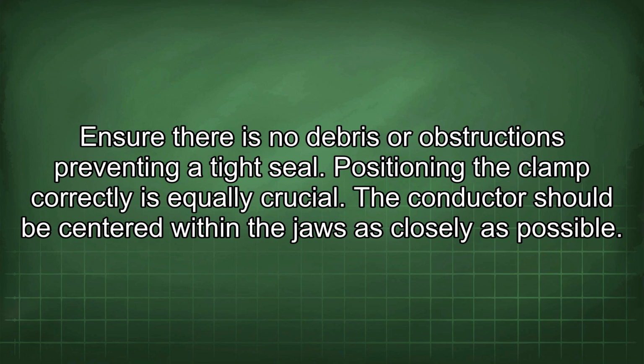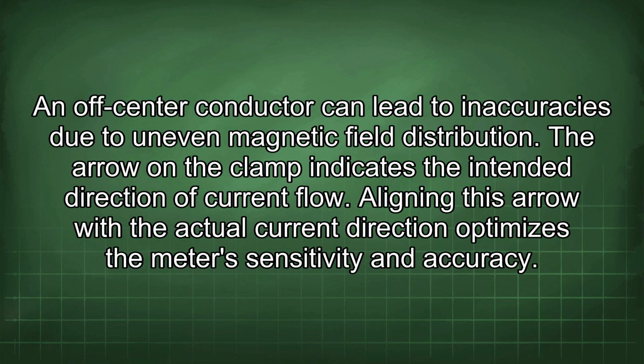Positioning the clamp correctly is equally crucial. The conductor should be centered within the jaws as closely as possible. An off-center conductor can lead to inaccuracies due to uneven magnetic field distribution. The arrow on the clamp indicates the intended direction of current flow. Aligning this arrow with the actual current direction optimizes the meter's sensitivity and accuracy.